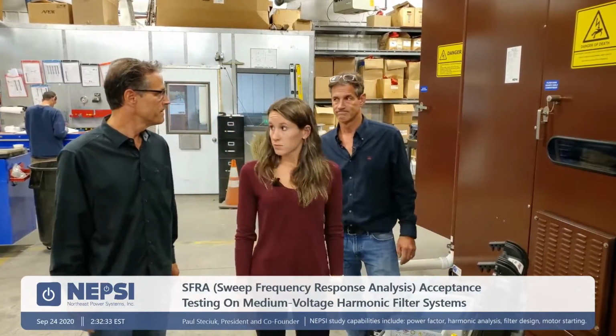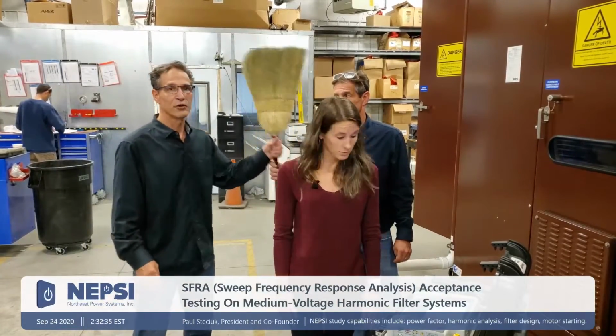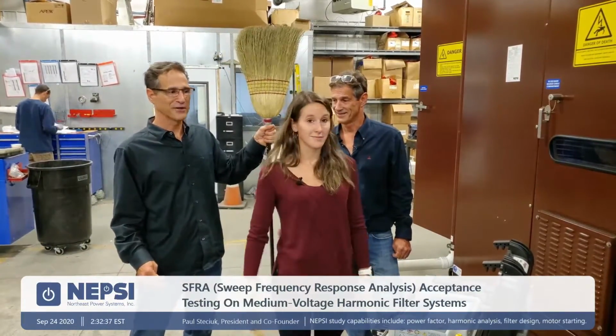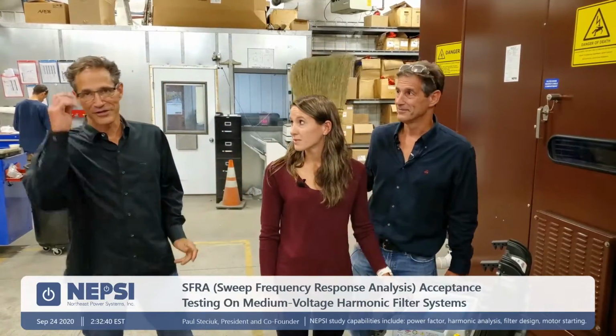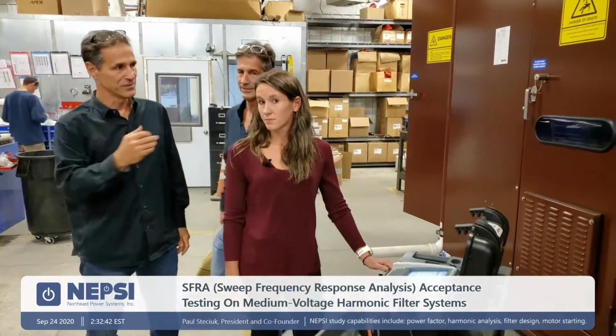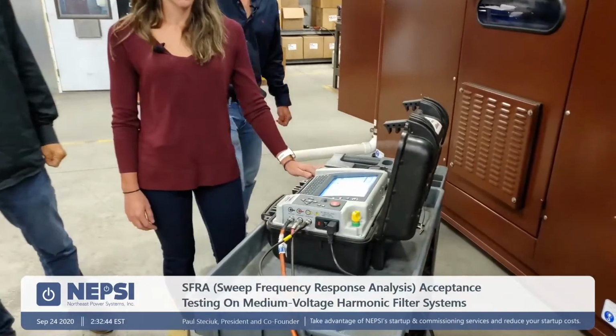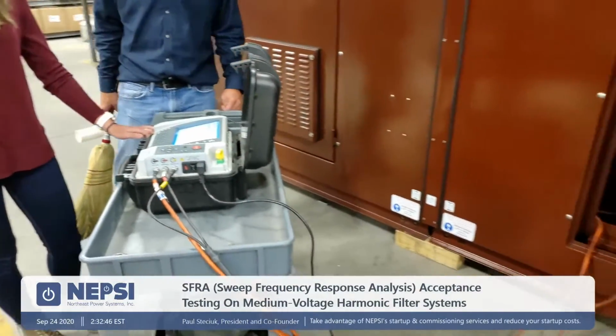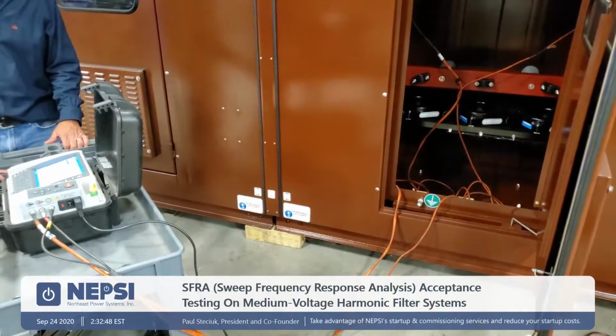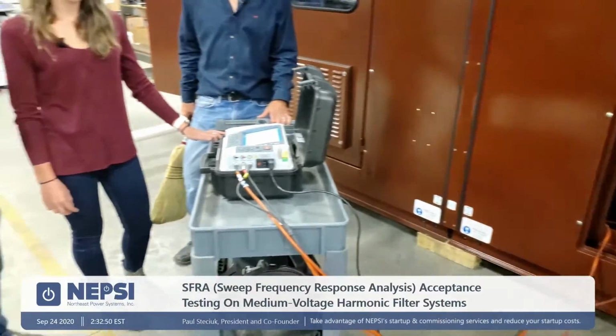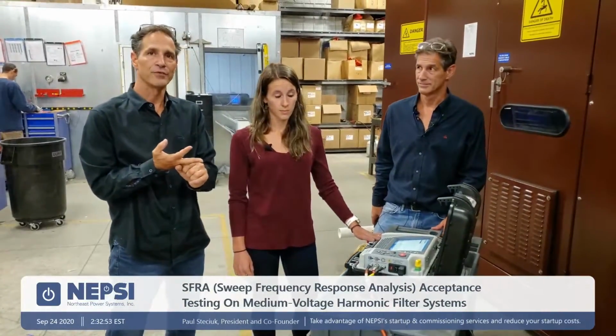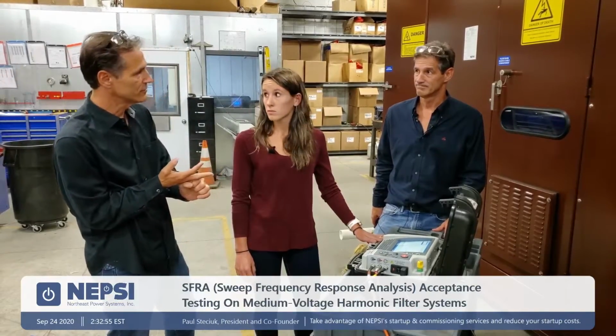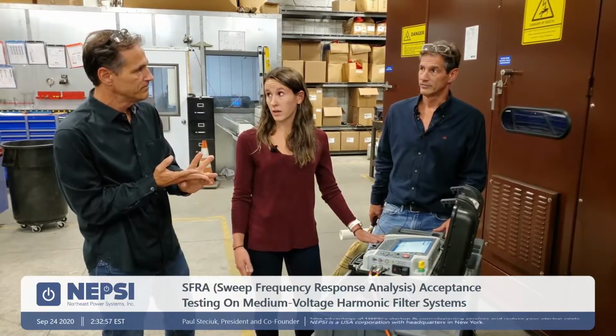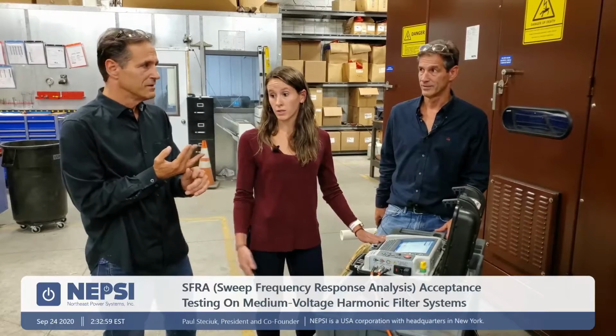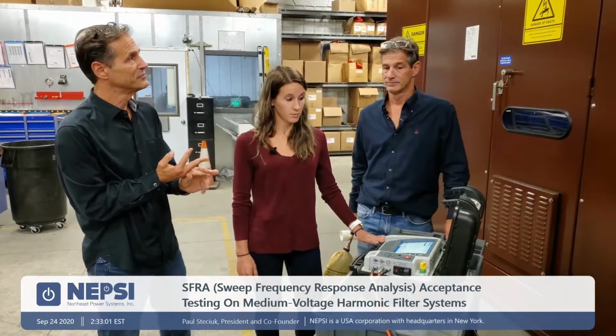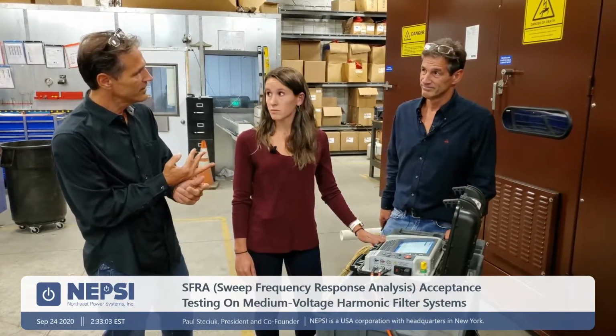Yes. So, okay. Sweep frequency response analysis. It's how we do it. It's how we check it at the factory. Jessica has been doing all of them for the past year or so. She's managed to pick up a lot of manufacturing errors at our factory: missing neutrals, tap reactors that are incorrect. Which other ones? We had a delta versus Y connection that was supposed to be Y connection. Delta versus Y. A misnamed capacitor, was that one?